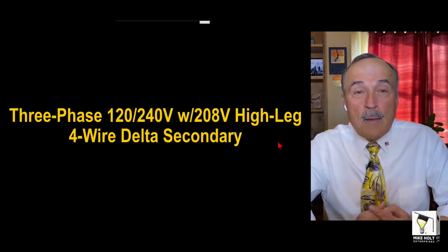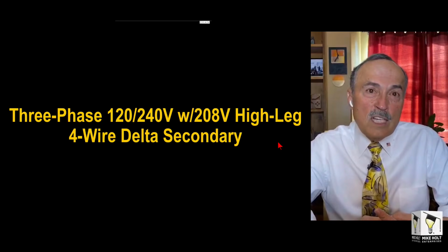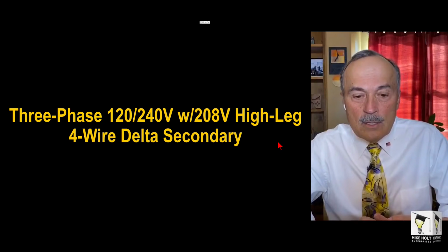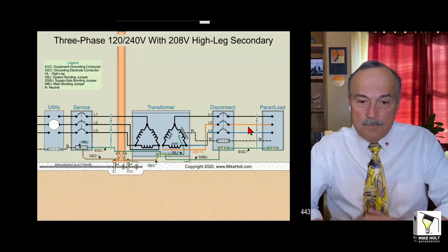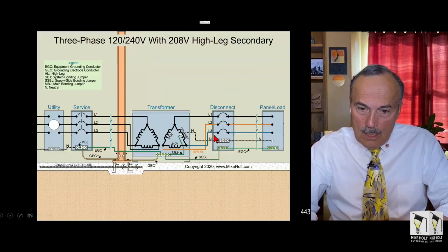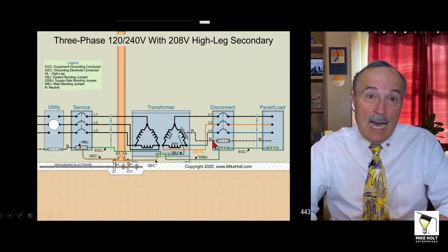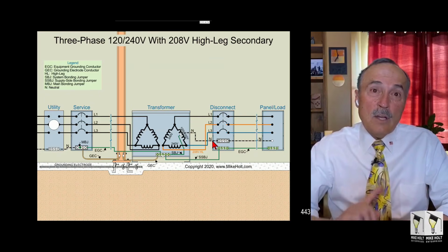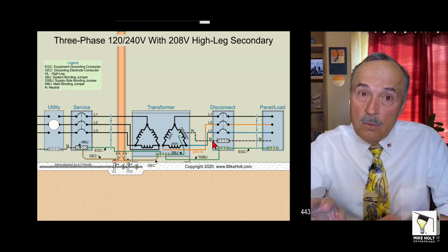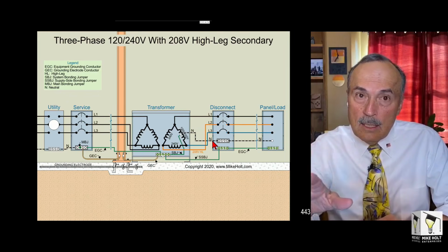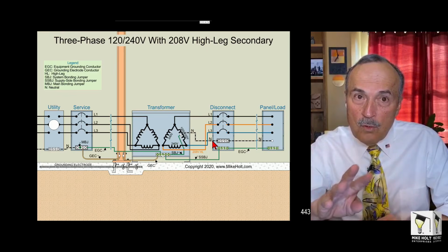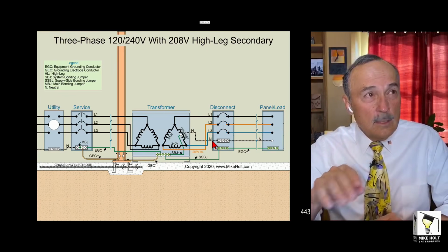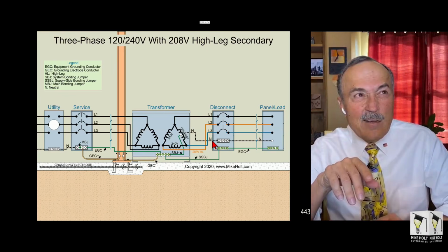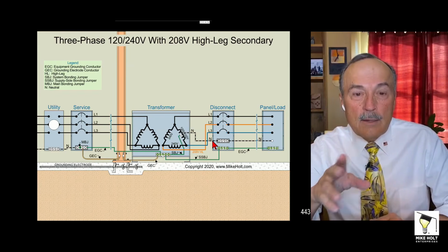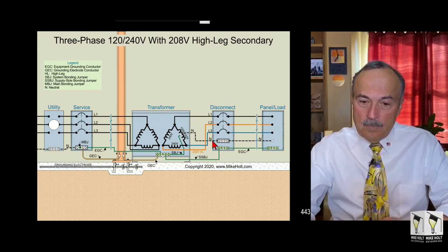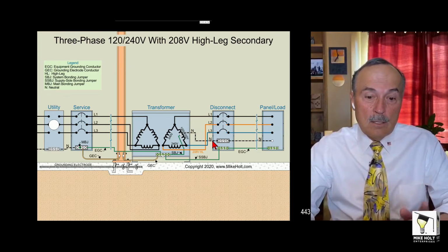All right, how about a 120/240 volt, 3-phase, 4-wire, high-leg delta system? Well, you've got line 1, line 2, line 3, and a neutral, and the high leg is required to be colored orange, placed on the B phase of a panelboard only, not disconnects and not meter enclosures, just panelboards. 408.3(E)(1) talks about the location, and 110.15 is about the color.